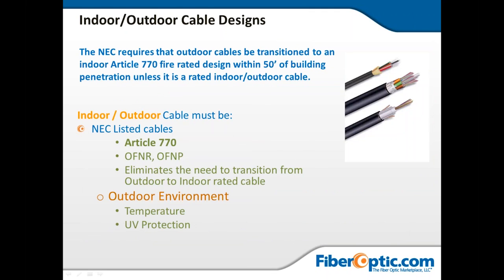Indoor-outdoor cable means the cable can be used outdoors and then run indoors for a certain distance depending on fire code — typically 50 feet. It can withstand UV, temperature, and weather outdoors, and then run inside as long as it reaches a junction box within 50 feet of the building, where you can then either break it out or splice in indoor cable. That's the benefit of indoor-outdoor cable designs.